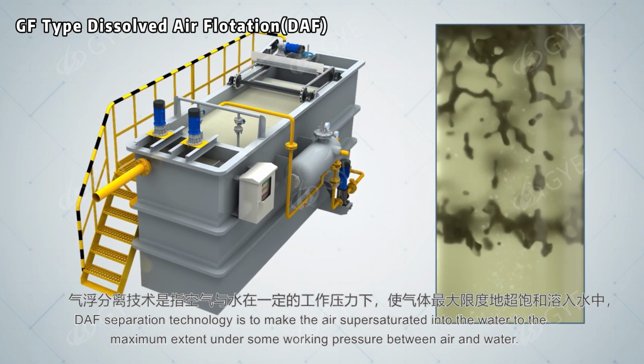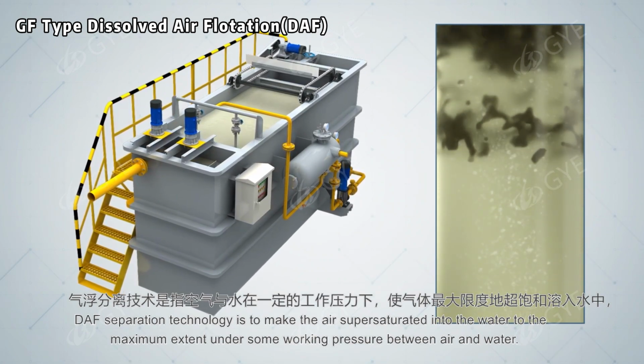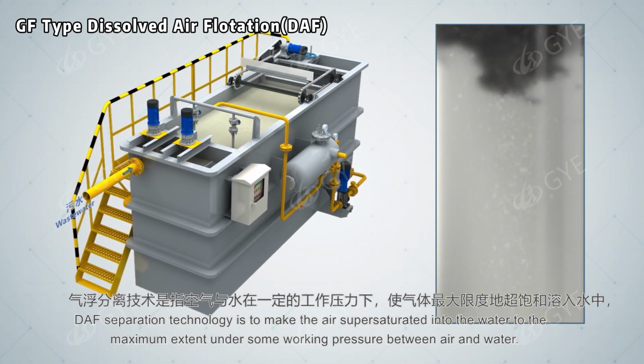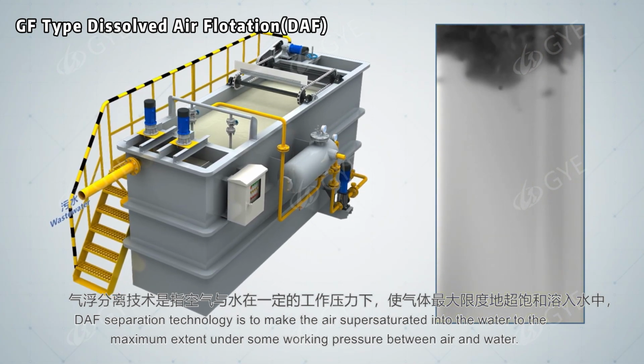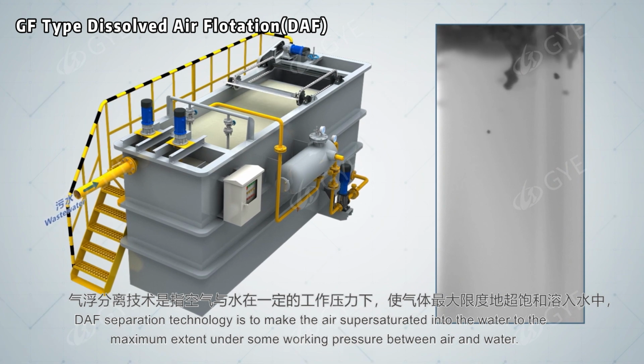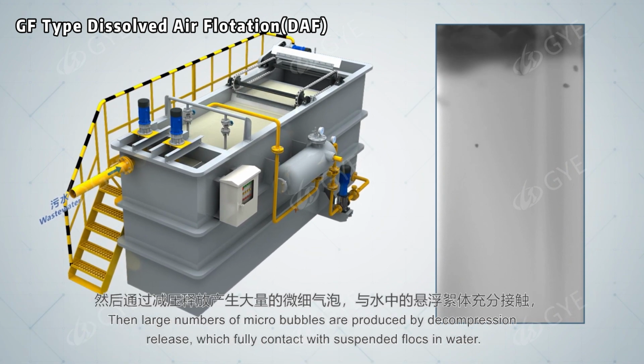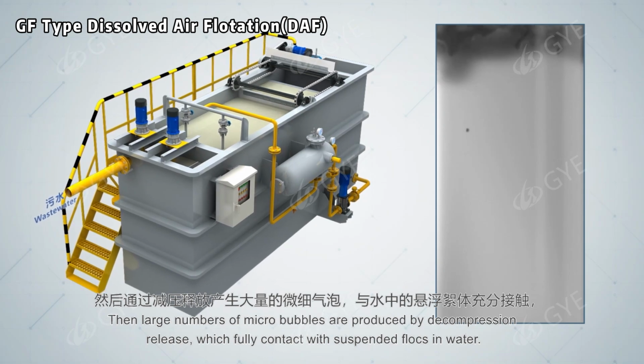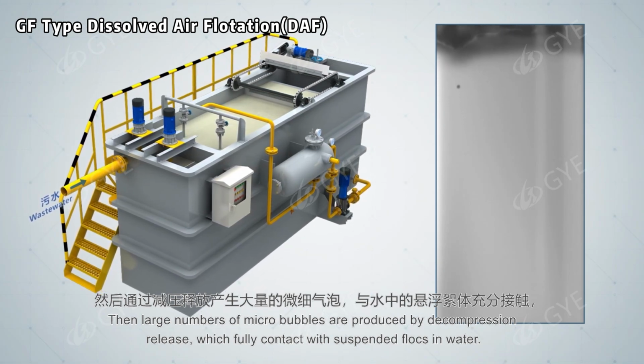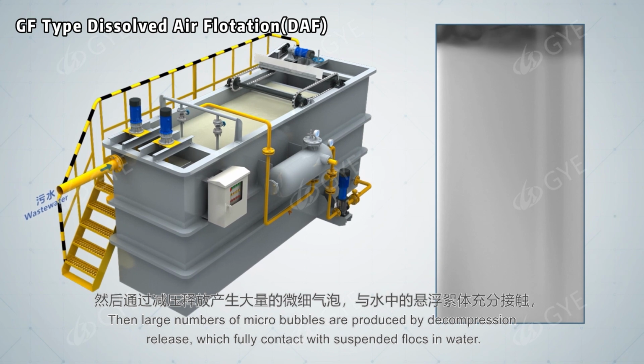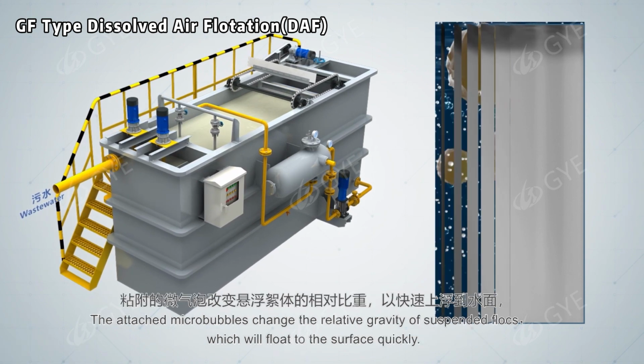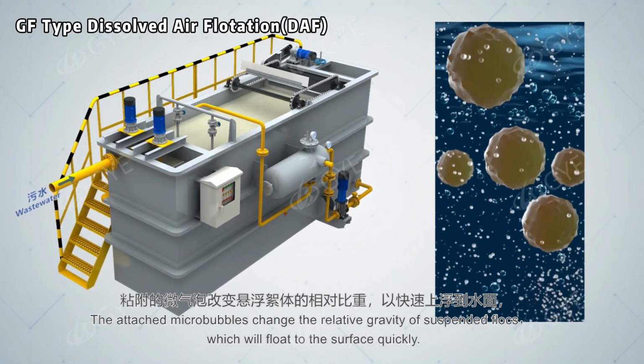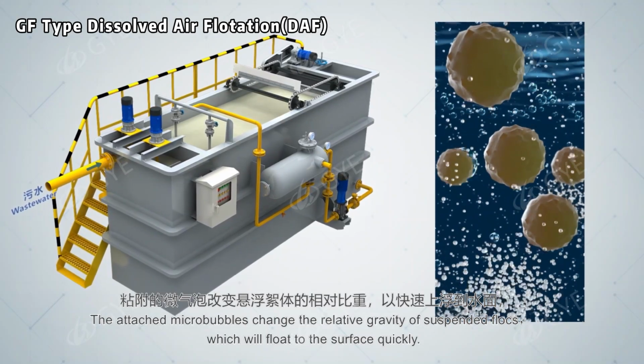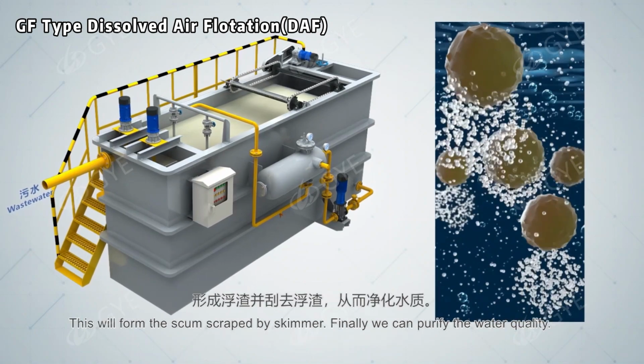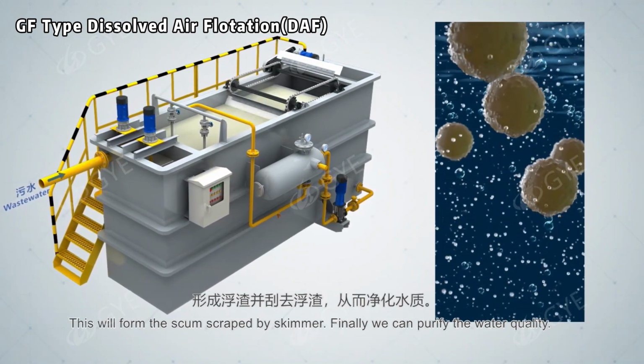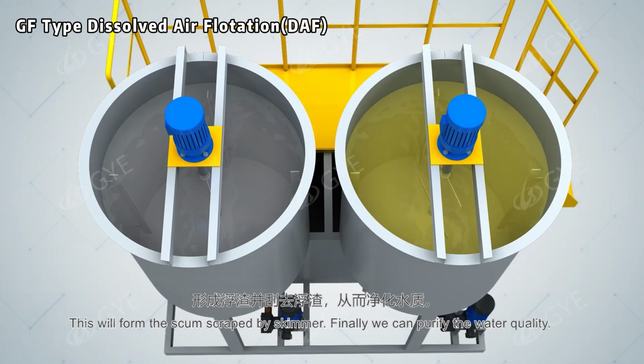DAF separation technology is to make the air supersaturated into the water to the maximum extent under some working pressure between air and water. Then, large numbers of microbubbles are produced by decompression release, which fully contact with suspended flocs in water. The attached microbubbles change the relative gravity of suspended flocs, which will float to the surface quickly. This will form the scum scraped by skimmer. Finally, we can purify the water quality.